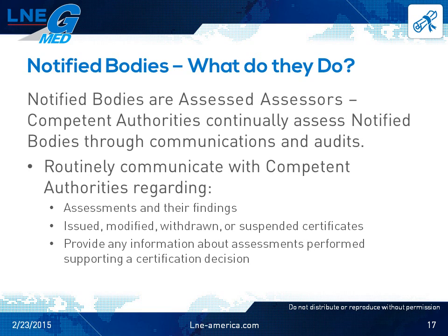Notified bodies, just like medical device manufacturers, have conformity assessments of their own that they have to follow as well. Competent authorities assess notified bodies routinely through a couple channels, mainly through communications and inspections. This means that a competent authority checks in with notified bodies to both ask questions and justifications for why a notified body made a specific decision, and the competent authority can inspect the notified body or witness an audit that it performs.